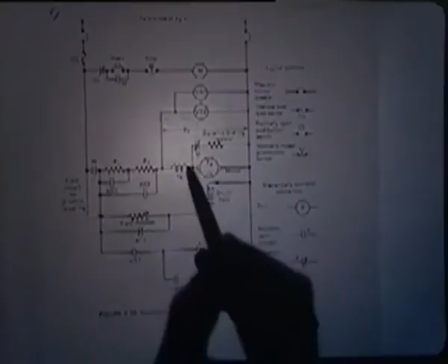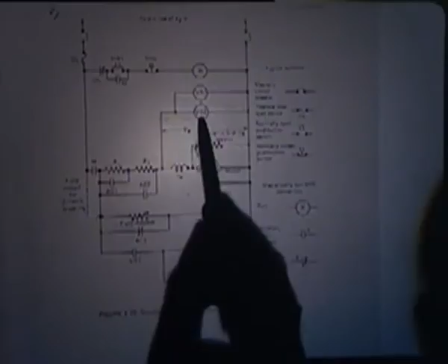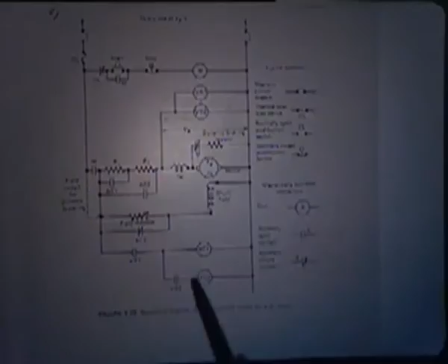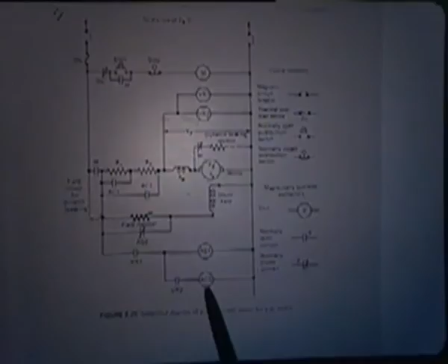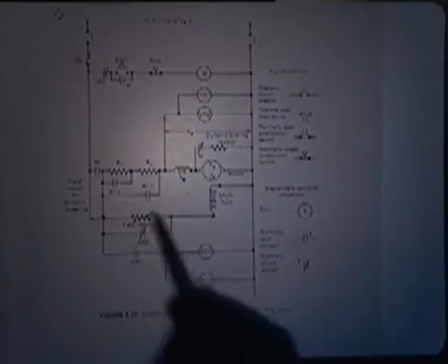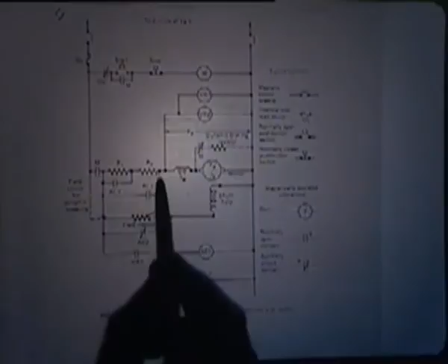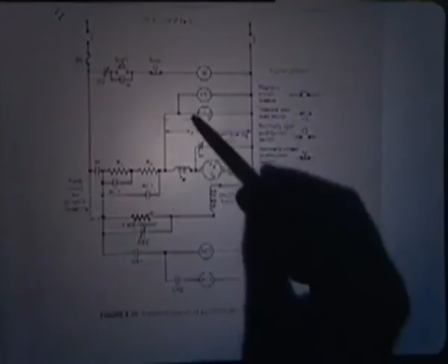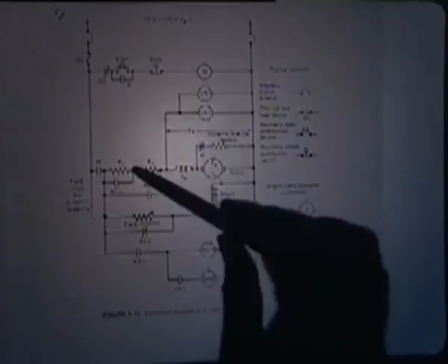Now as R2 is in the picture, after some time as the voltage goes higher to a value, say VR2, the VR2 coil gets energized. When the VR2 coil gets energized, this contactor gets closed. When this contactor is closed, the coil AC2 gets energized. When AC2 gets energized, the corresponding contactor AC2 closes. So the second resistor also gets short circuited. So you find that fully automatically, as the voltage goes to a certain value, both the resistors will be out of the circuit.